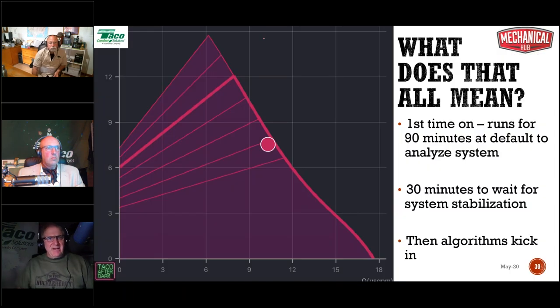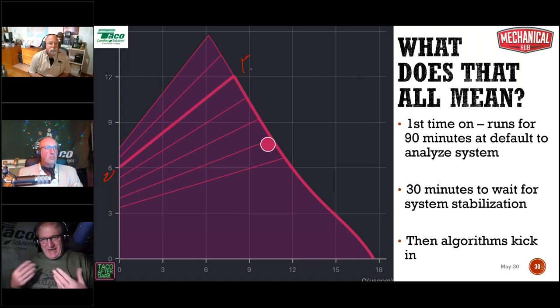So what does it all mean if you're going to use this in that type of system? The first time the pump comes on, it's got to run for 90 minutes at its default setting, which is this setting right here, to analyze the system and get a good idea of what's going on. Then there's another 30 minutes on top of that for system stabilization, and that's when the algorithm kicks in. Then it says, do I have to go up? Do I have to go down? Where should I go?